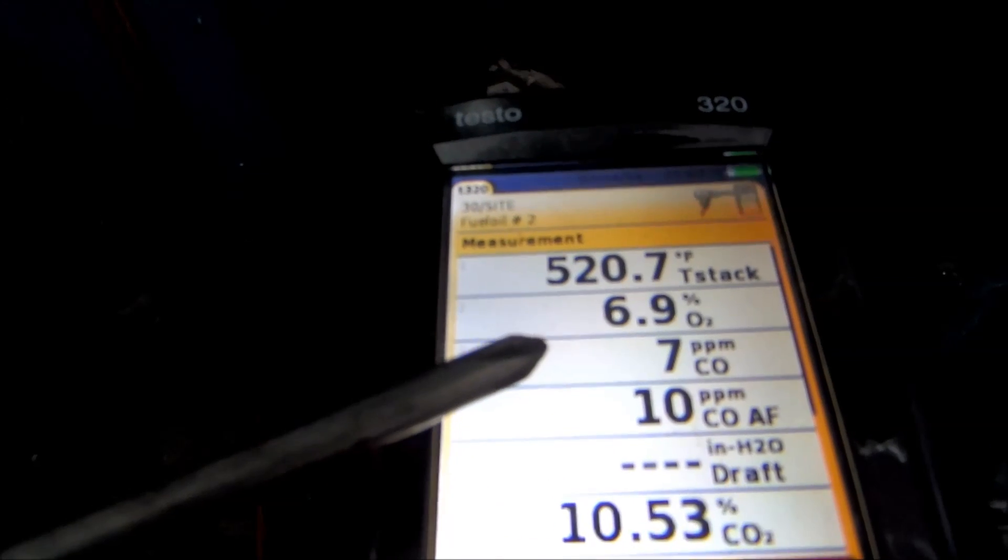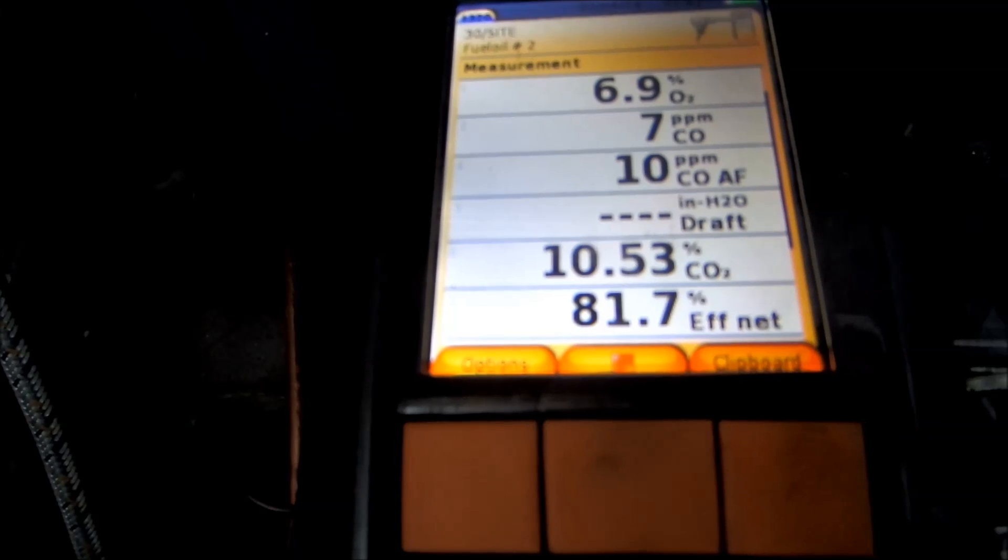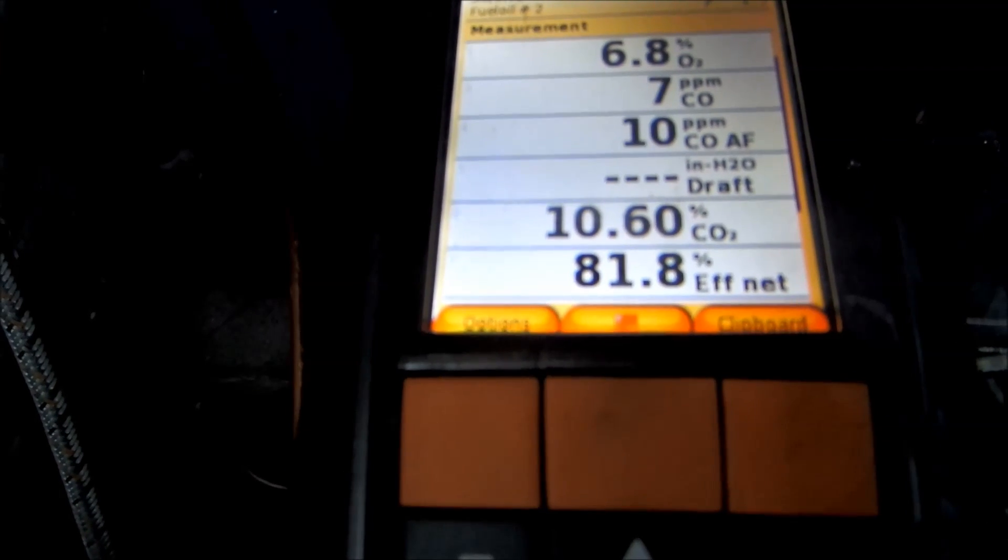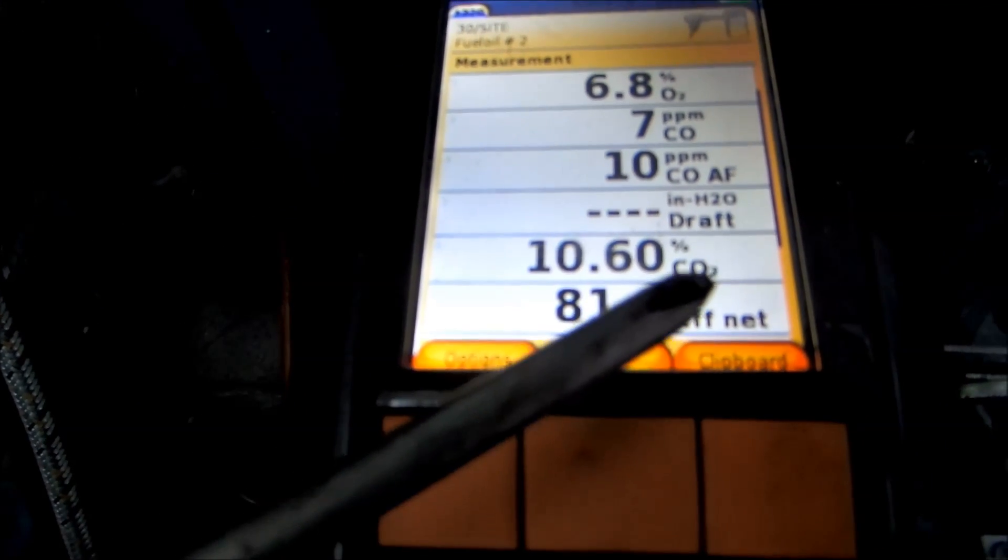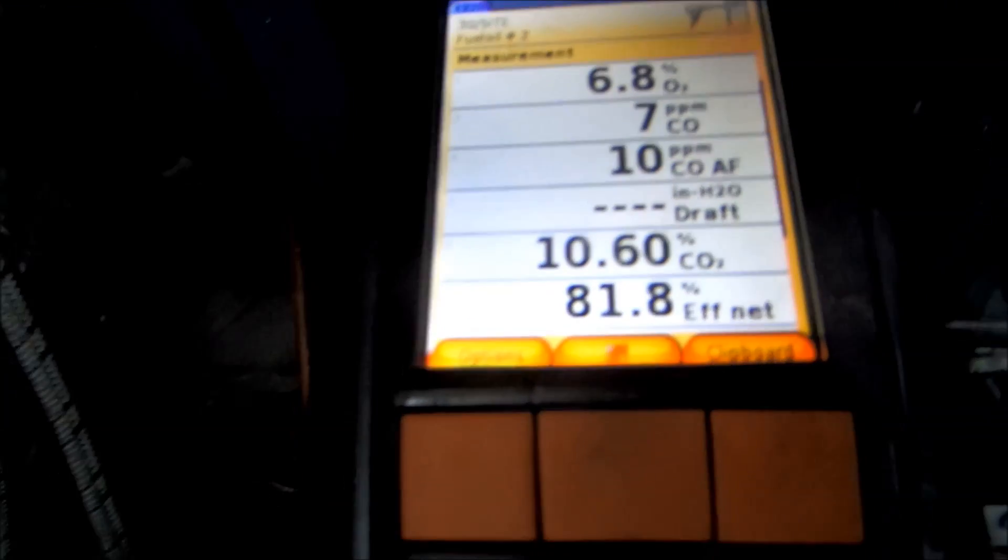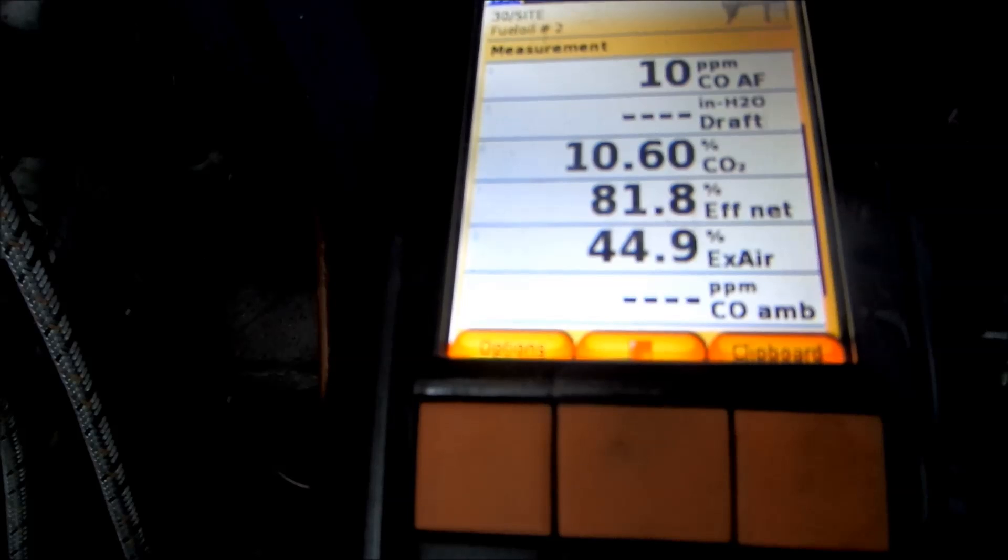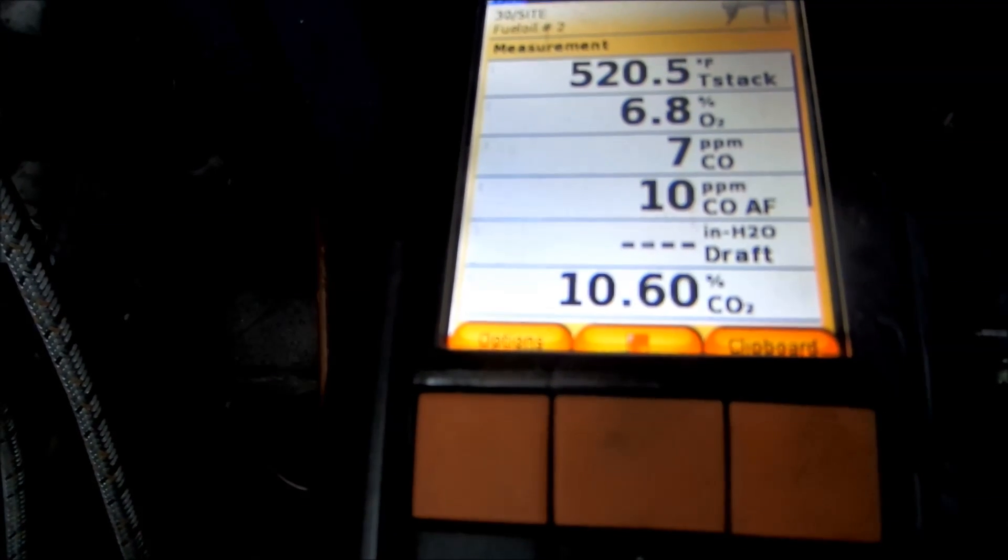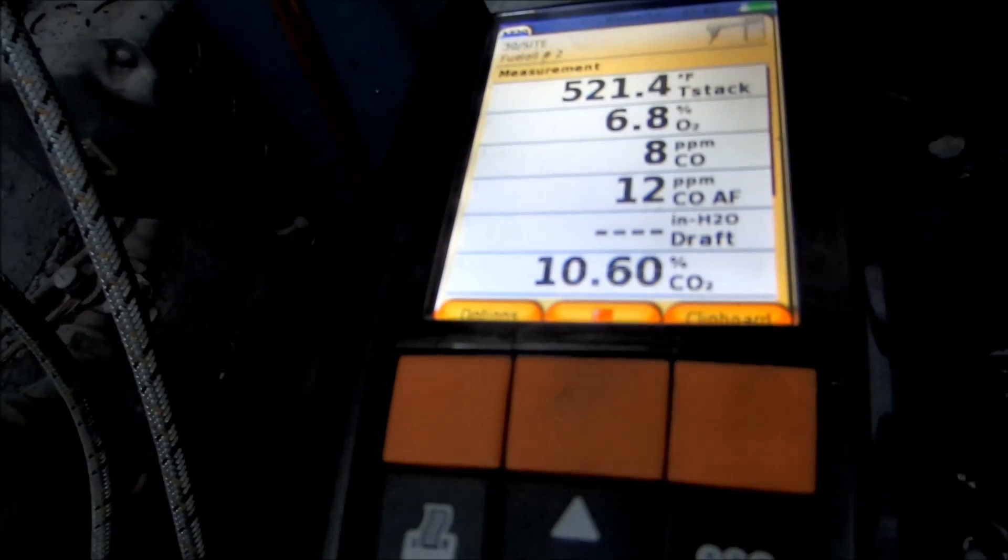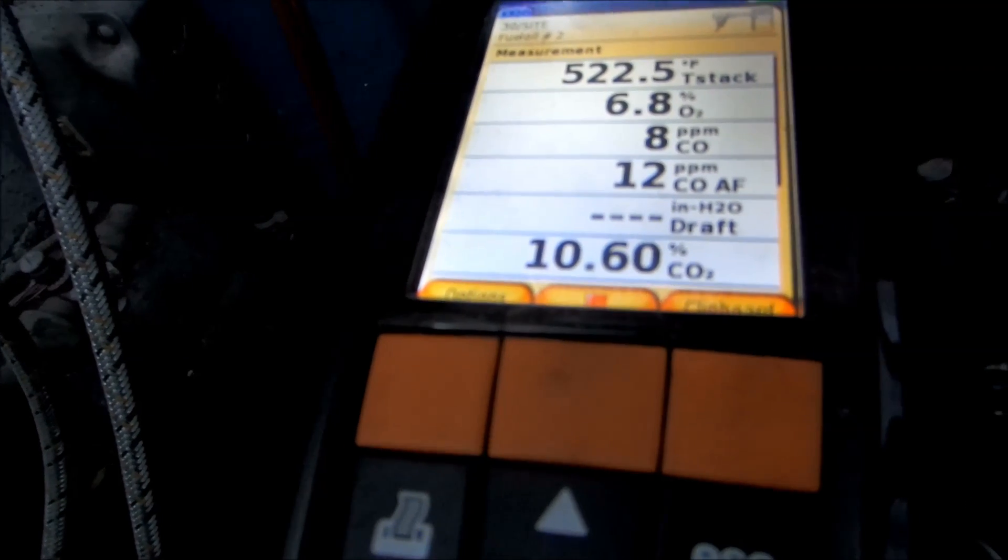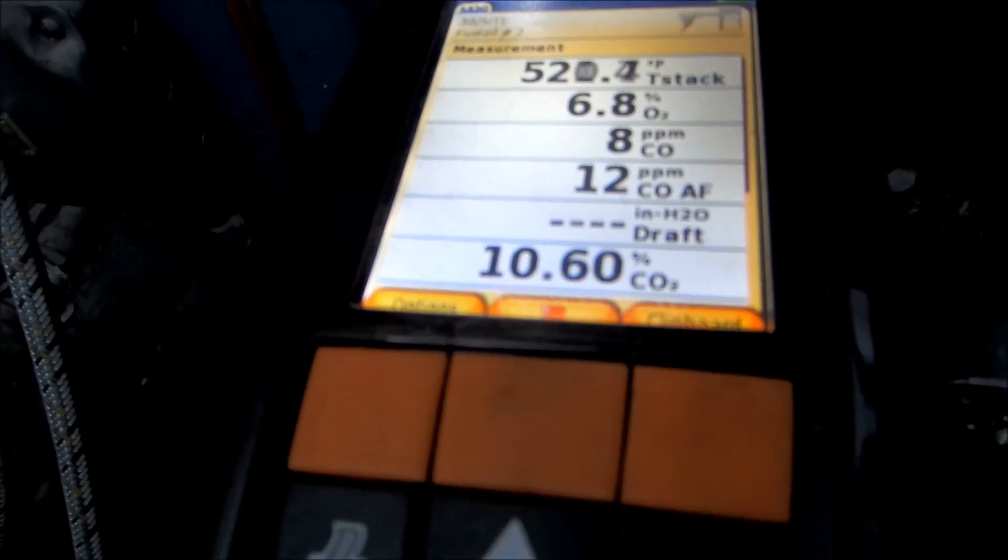81.8%. How they determine that is stack temperature and CO2 will give you efficiency. That's how they determine that. I've got a chart that they go by on that too. I'm fine with that, 10.6 CO2.